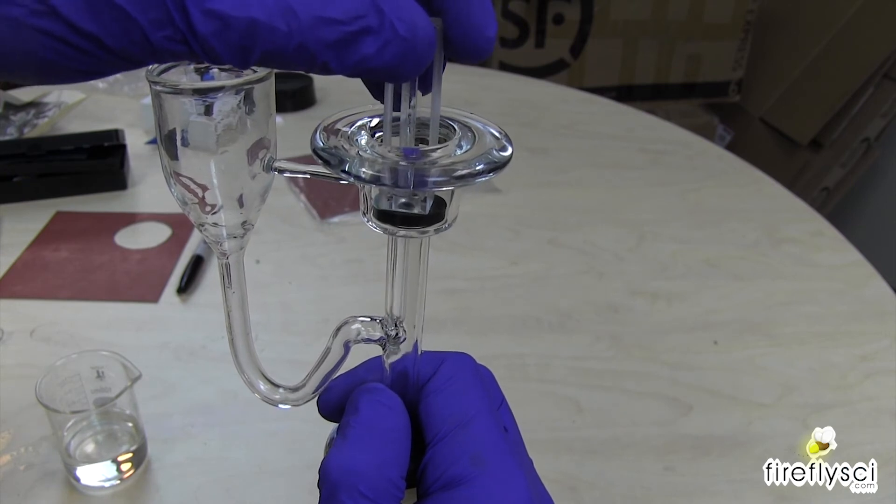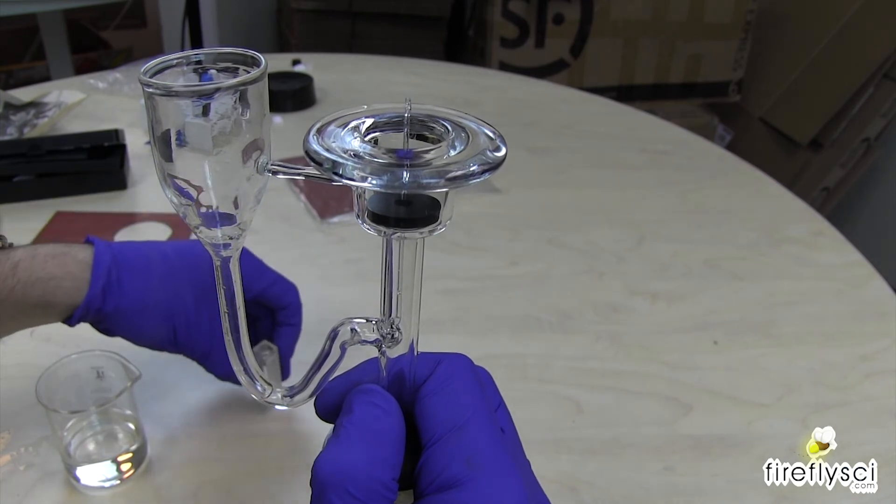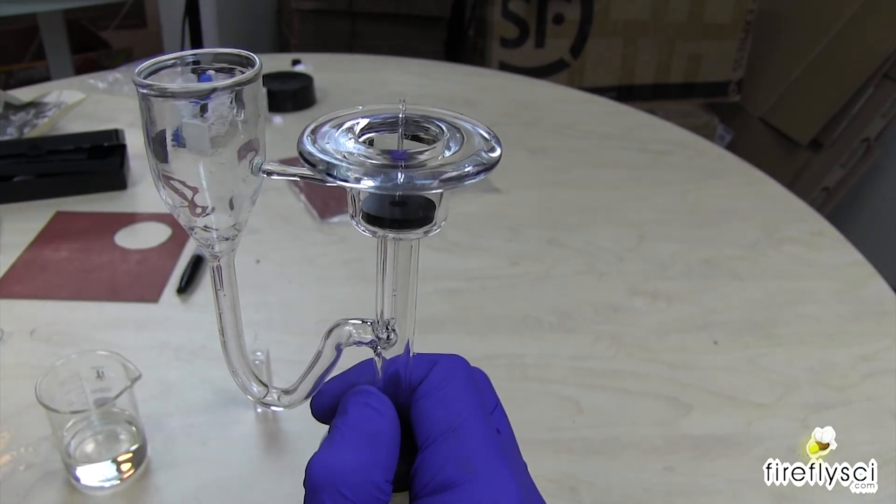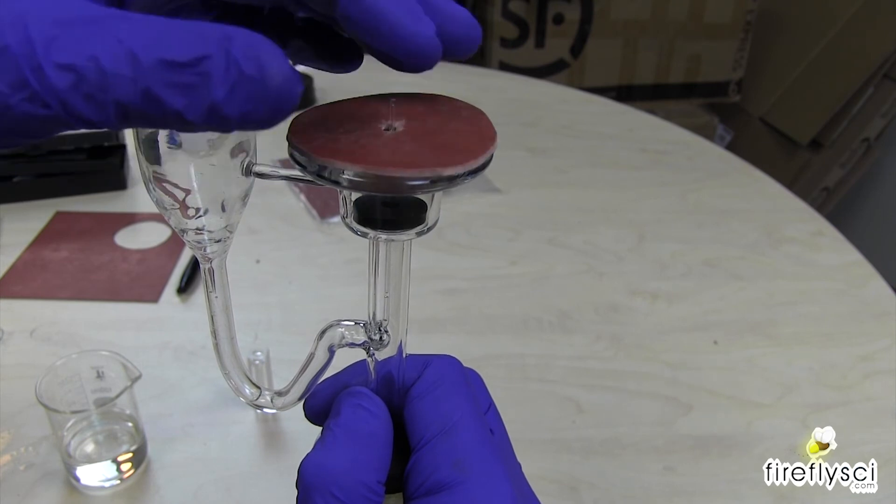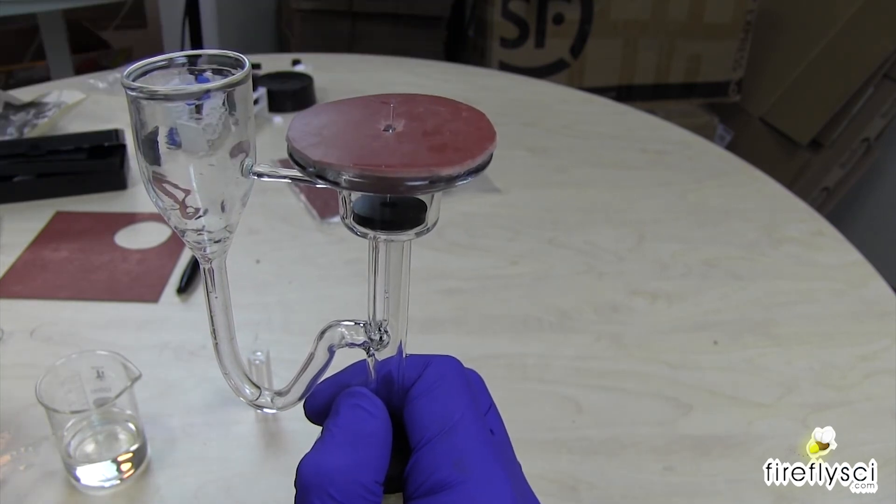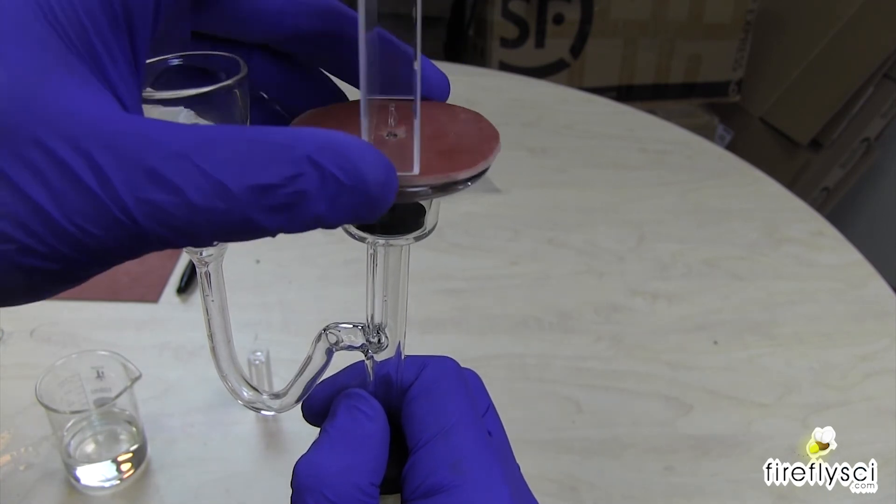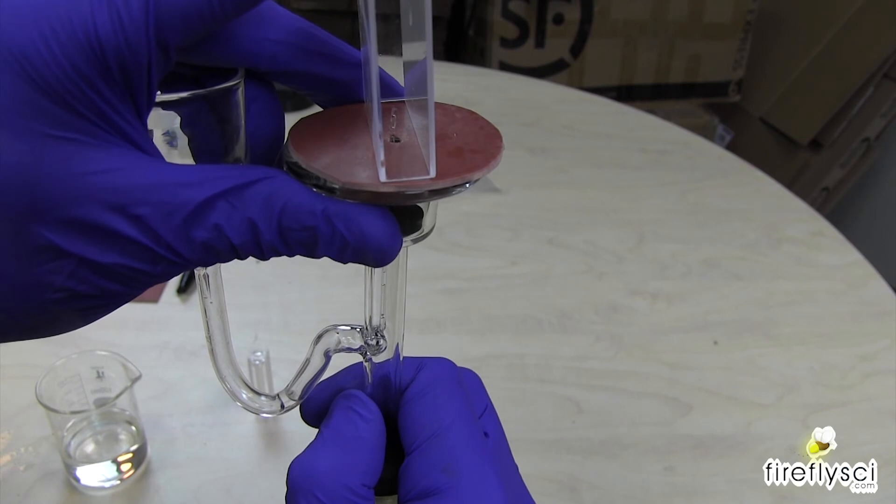Which makes me feel. Oh, it's got really good suction on it too. Now the question becomes, why is the large light path cell not working? Put on my big disc there. The only thing I think of is that this rubber is not making a tight enough seal. And in which case, I have to get a new gasket here.